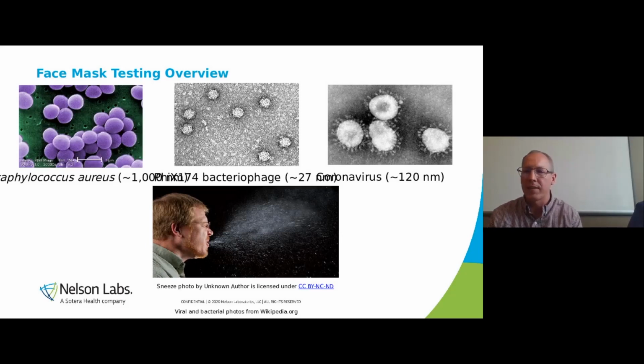So this graphic here is showing the size of the Staphylococcus aureus that we're using in this test. It is approximately 1,000 nanometers. So it's almost 10 times larger than the coronavirus, which is approximately 120 nanometers. Why is this bacteria sufficient to use in this test if the coronavirus or influenza virus or other viruses are so much smaller? As you can see in the picture below, as someone sneezes or coughs or speaks, it's the water droplets that are coming out of the mouth that the bacteria or the virus are attached to. There are no free-floating viruses or bacteria in the air. They're always attached to some kind of particle, whether it be a fluid or a dust or hair particle or something. And so in these tests, we're not measuring the size of the actual bacteria or the virus. We're actually testing the size of the particle that these organisms are attached to. So that's why it is appropriate.